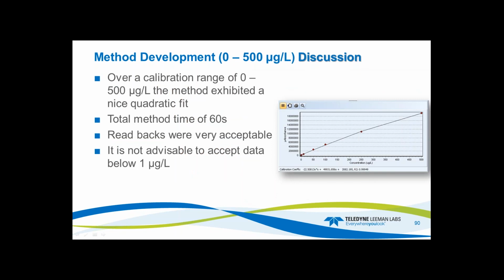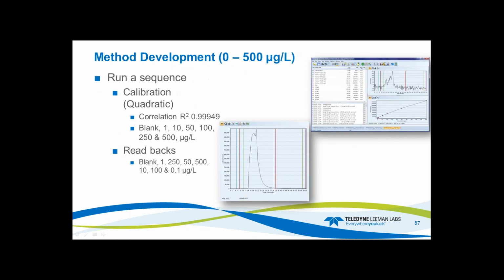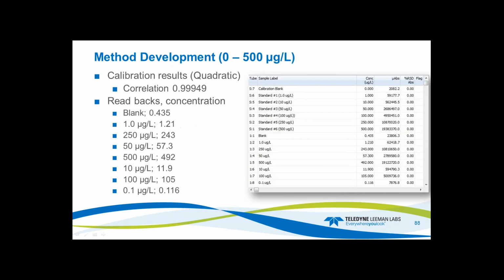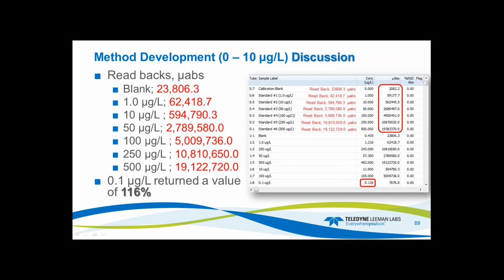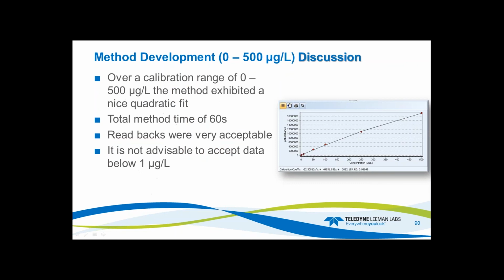So over that calibration range, it exhibited a nice fit. My total time was 60 seconds. The readbacks were very acceptable. And again, it's not advisable to run data below 1 µg/L. But let's just pop back here real quick. You can see that you can run it. The readbacks are good, and it's very easy to do. It took me like 5 minutes to develop the method, and away we went.